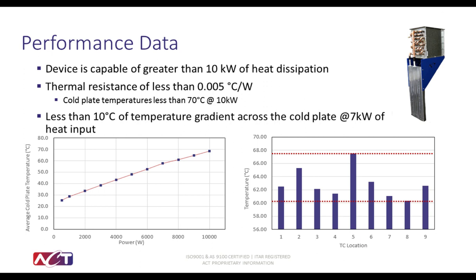Another benefit to using a loop thermosiphon is that due to the vaporization happening within that evaporator plate, the temperature of that evaporator plate is held relatively constant from end to end. In a typical pumped liquid system, you'd anticipate quite a temperature rise from end to end with a heat input of 7 kilowatts. However, across this plate, due to the two-phase operation, we see only about an 8 degrees Celsius spread. Loop thermosiphons are excellent devices to transfer kilowatt-level thermal loads with very low thermal resistance in your applications.